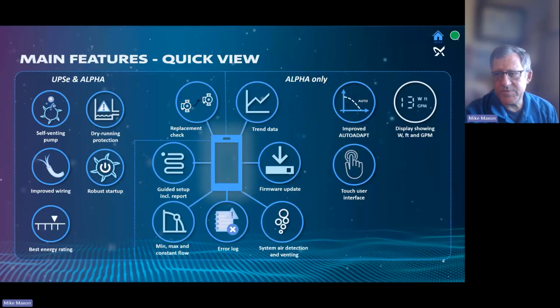We have new auto adapts. On the Alpha, there are 3 auto adapt settings: 1 constant curve auto adapt, 1 for constant pressure, and an auto adapt for proportional pressure. The Alpha is a touch screen, touch on the faceplate of it. It's not buttons, it's just simple touch. And it does have a display with watts, feet of head, and flow. That is changeable by simply touching the icon next to the number, and it'll toggle through the different values.